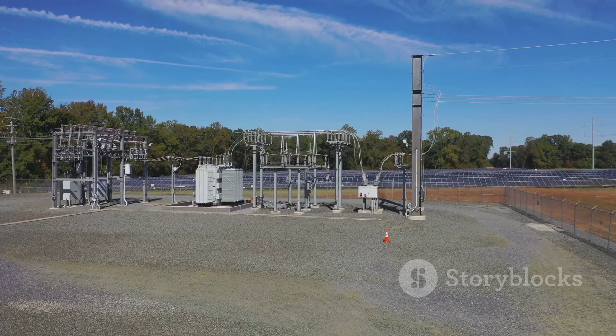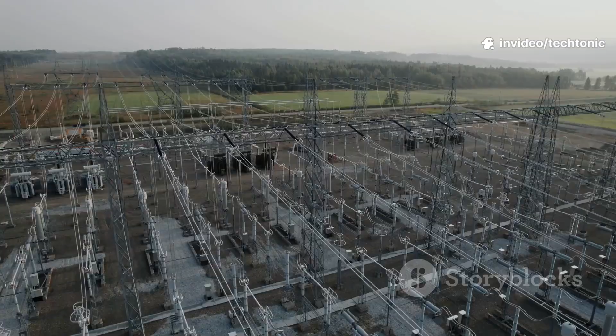Substations combat these dangers with grounding grids and layers of crushed rock, which insulate workers from dangerous currents. These measures flatten voltage ripples and reduce risk. Managing the path of electricity is key to safety. Grounding systems are engineered to protect people from invisible threats. Always stay clear of downed lines and energized objects. The ground itself can be dangerous in a fault. Safety comes from understanding and respecting these risks.